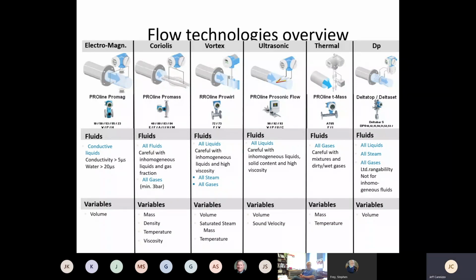So again, mag meters, conductive liquids, gotta have some conductivity, typically above 5 to 20 microsiemens, which tap water usually starts about 35 or 40 and goes up depending on where you're living and where you're getting your water from. They are a volumetric meter. Coriolis meters, good with all fluids. You have to be a little bit careful with air entrainment. But they are mass meters, and they are multivariable meters. They'll give you density, temperature, and viscosity.